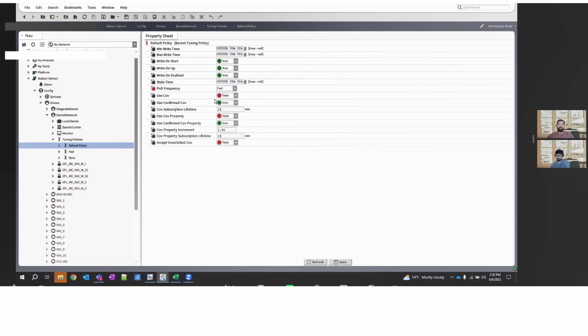The other option available here is use COV. Instead of going with polling, you can use the COV option and make it true. But in that case, you need to make a note of the COV property increment. You need to define the COV increment for each individual type of point. As an example, for temperature you could say 0.2, and then the value should update at that increment. But for pressure, the value will vary, and so for other points. So in that case, you will have to create multiple tuning policies. Once you do that, we'll stick to poll frequency in this case and not COV. Then, with the thumb rule, we will assign the points.